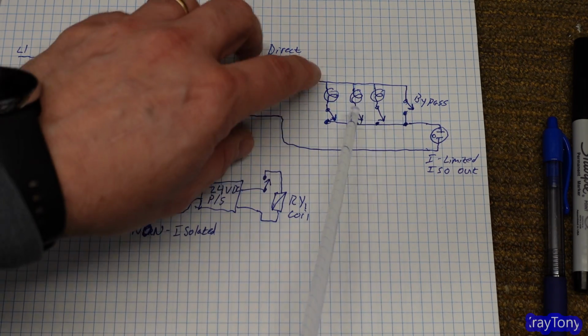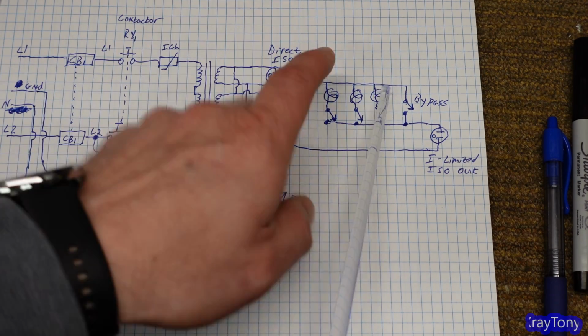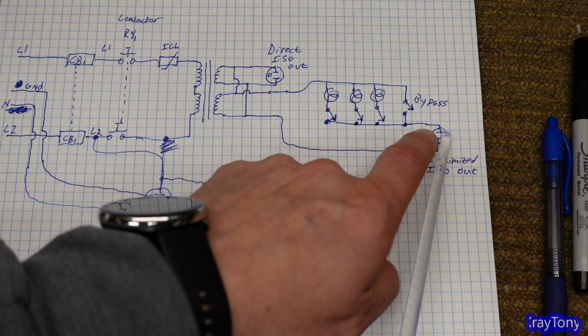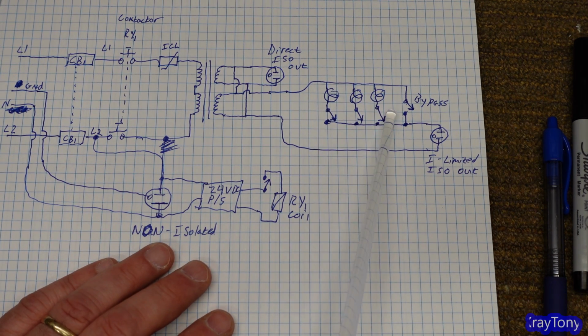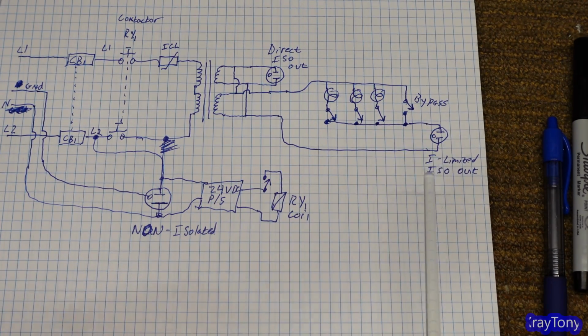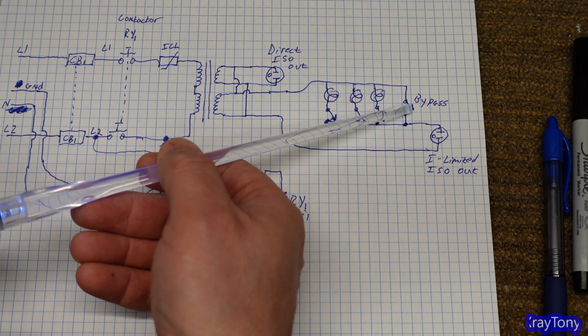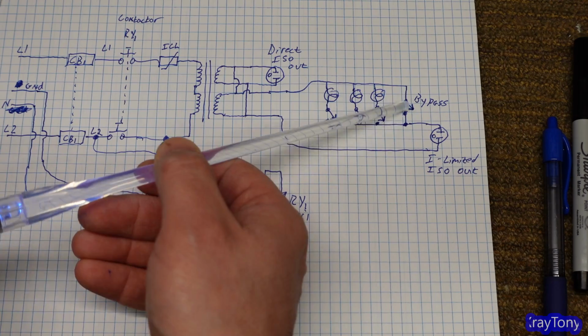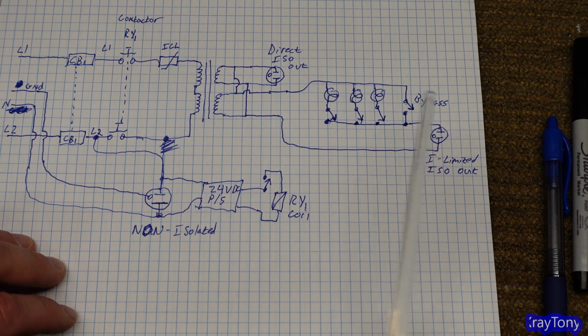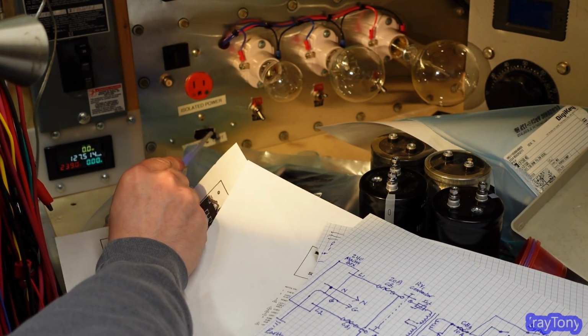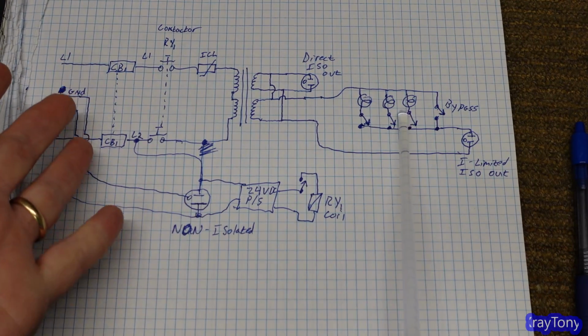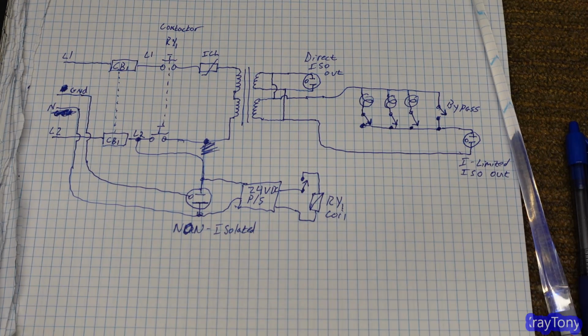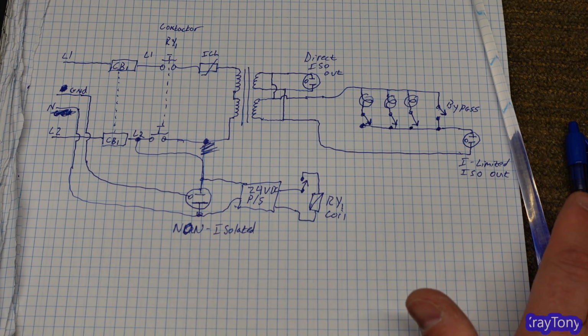As I switch these in, I put more and more load. These bulbs will be in parallel, allowing more and more load to go into the device under test. So I can limit the current a lot with one small bulb, or put multiple bulbs in parallel, allowing more current to flow. In addition, I can hit this bypass switch, which is a 20 amp rated switch, for a direct connection to this outlet. So that's what that is, and that's that big switch down here at the bottom. That's how that works. So when you see this, that's, in a nutshell, how it's wired up. I'll take a couple pictures and put them up on the screen so you can actually look at it now.